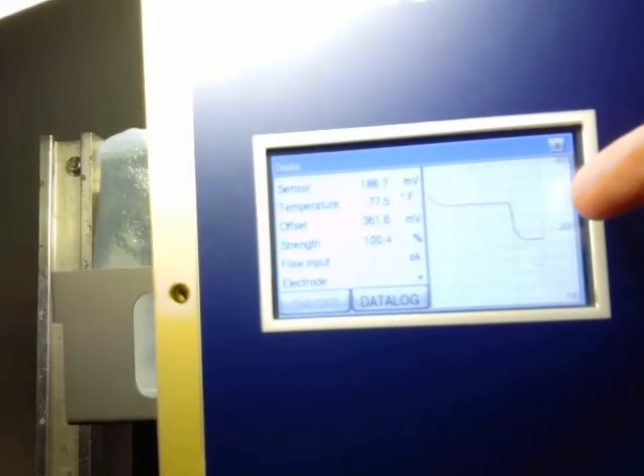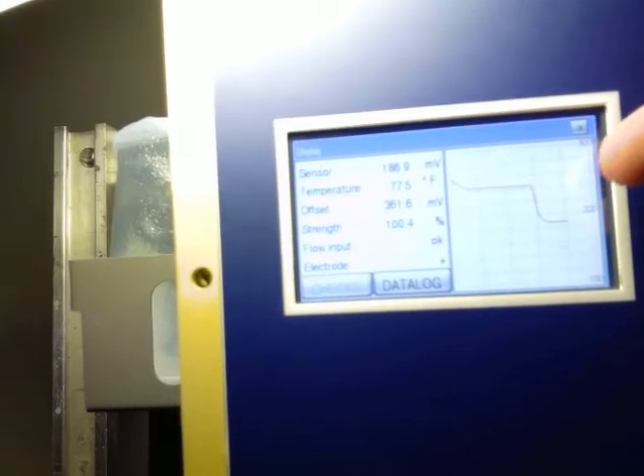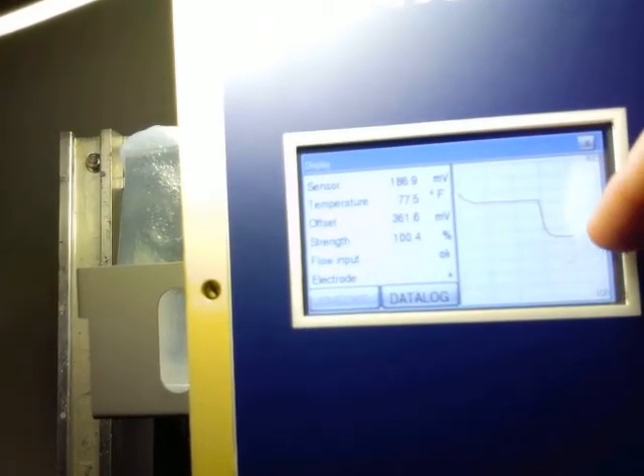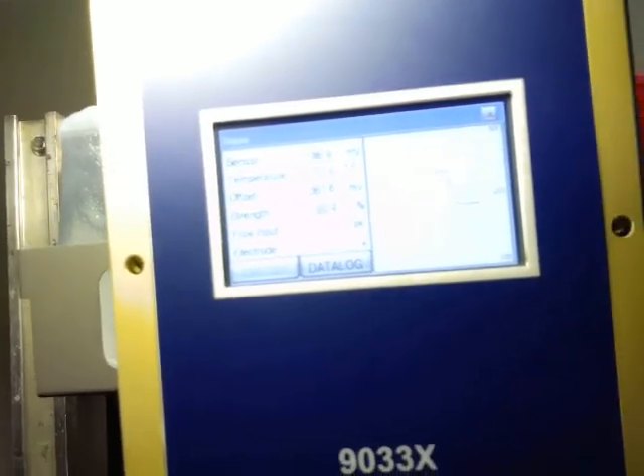And that step change, again, was the number that Joe was talking about, 60 millivolts difference. So again, the number where it starts and where it ends is not as critical as seeing the change between the two. So when it runs its calibration, the number that it's basically going to calculate is this strength or slope value that we've talked about. And that's kind of the determination of whether we get a failure or a passing cal. And what it's looking for, it's basically comparing to a theoretical perfect slope. Say, hey, if everything's right, you get 100%, and that'd be basically lining up with a perfect theoretical curve.